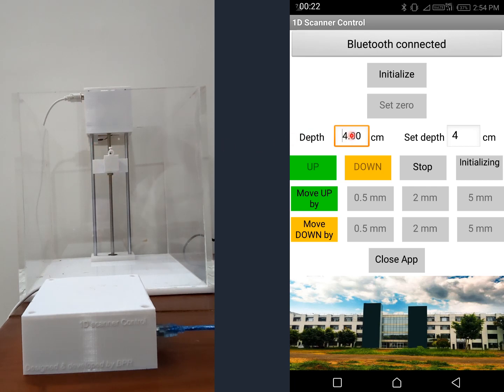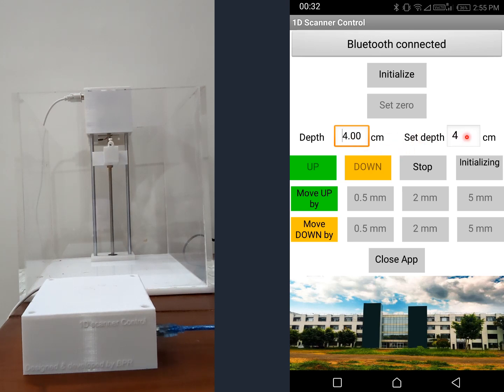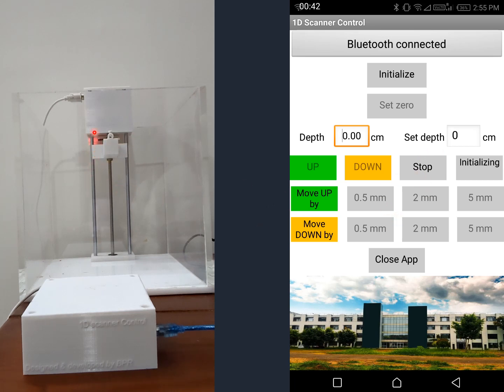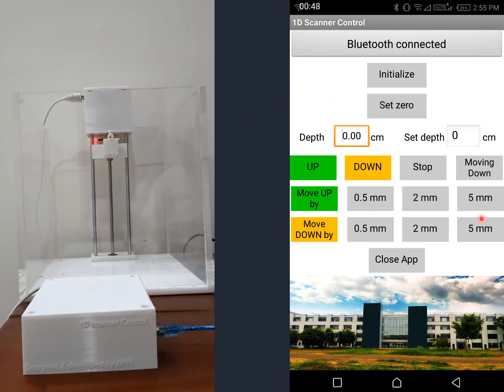The depth is shown as 4 and doesn't change because the system does not know the actual depth — it has not been initialized yet. This is the actual gap, and this is the set depth. You can set zero at any point, and from that point the depth is shown here. Now it is going to reach the sensor — the hall effect sensor has detected the magnet, so initialization is complete. All controls are now activated.